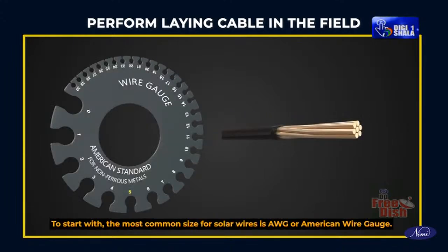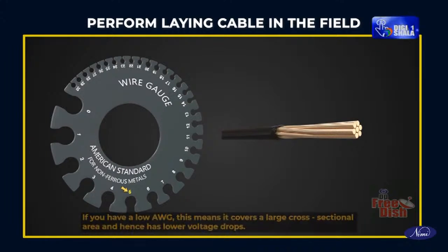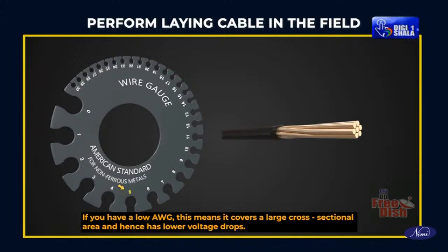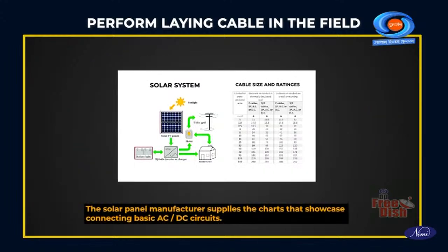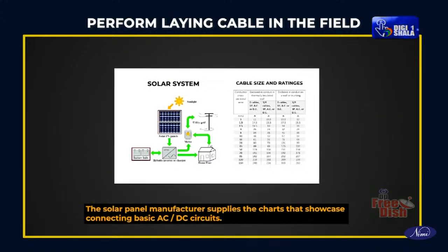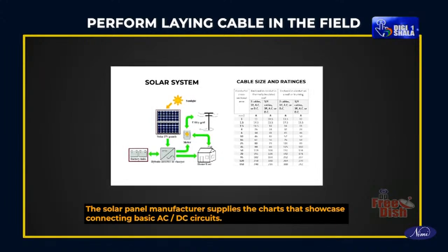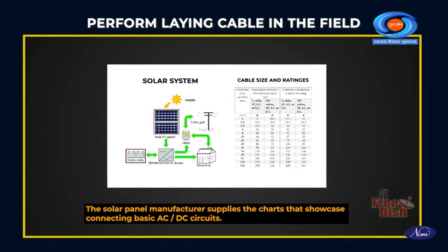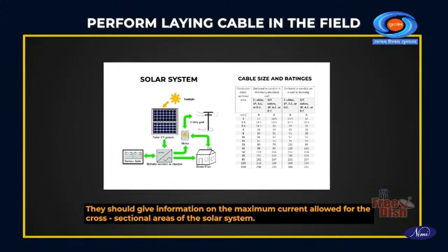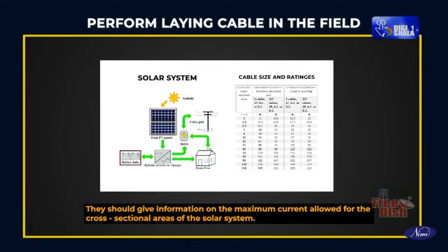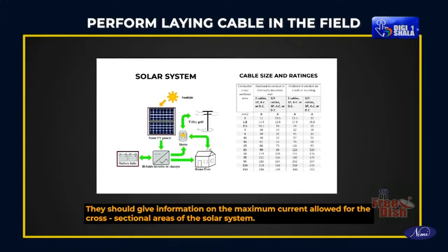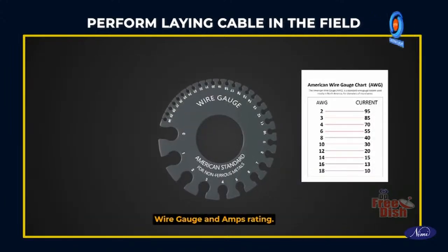To start with, the most common size for solar wires is AWG, or American wire gauge. If you have a low AWG, this means it covers a large cross-sectional area and hence has lower voltage drops. The solar panel manufacturers supply the chart that showcases connecting basic AC or DC circuits. They should give information on the maximum current allowed for the cross-sectional areas of the solar system. Wire gauge and amps rating.